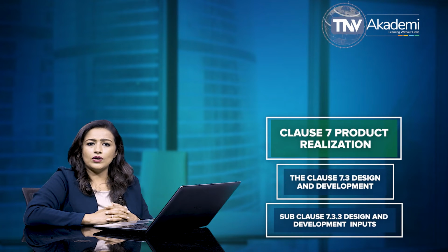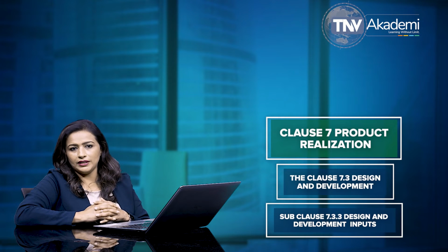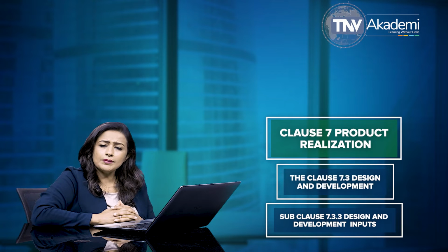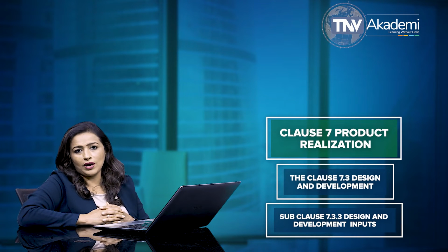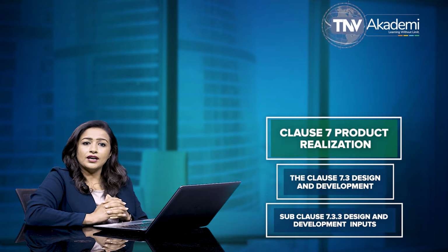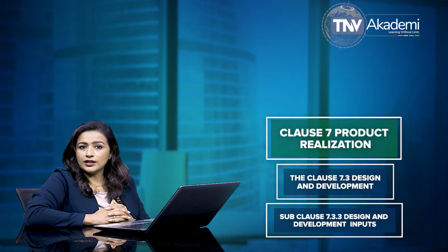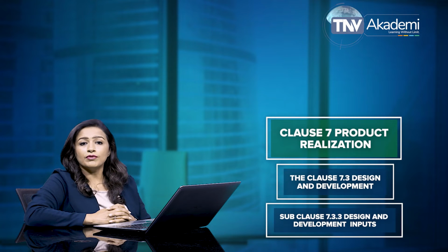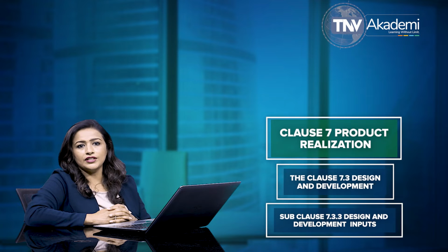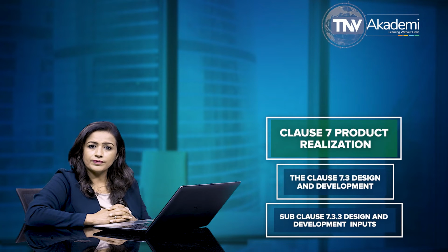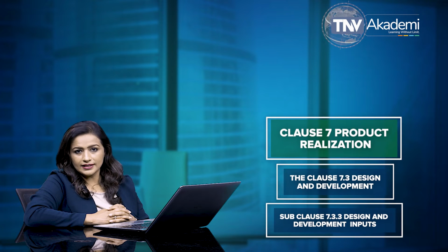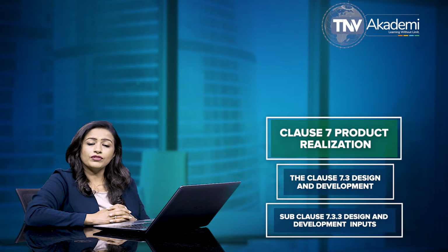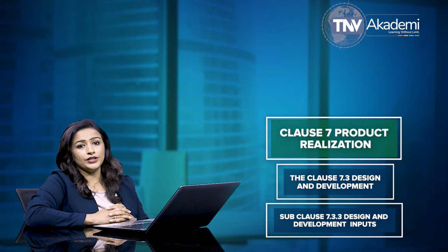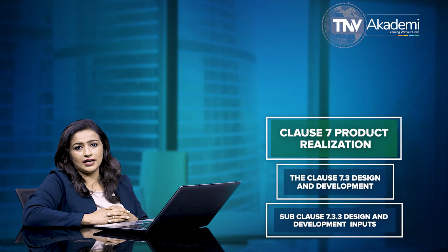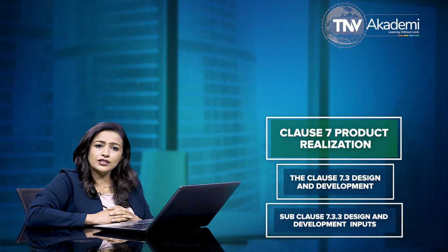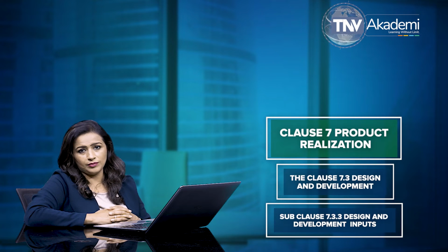Let's talk about subclause 7.3.3, Design and Development Inputs. This subclause says that inputs relating to product requirements are required to be determined and records maintained. These inputs are required to include functional, performance, usability, and safety requirements according to the intended use, applicable regulatory requirements and standards, applicable output of risk management, as appropriate information derived from previous similar designs, and other requirements essential for design and development of the product and processes.